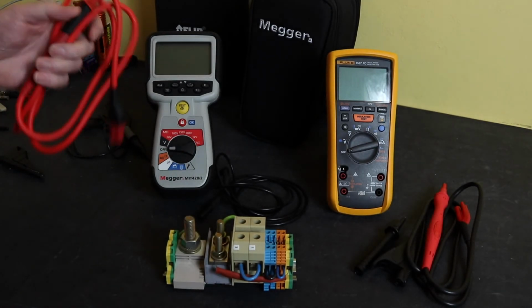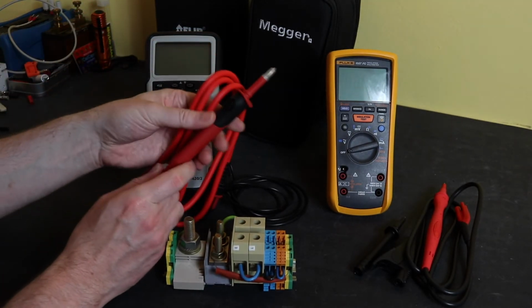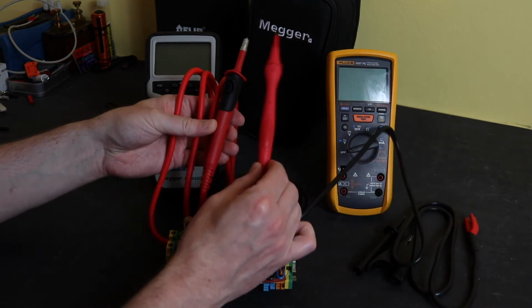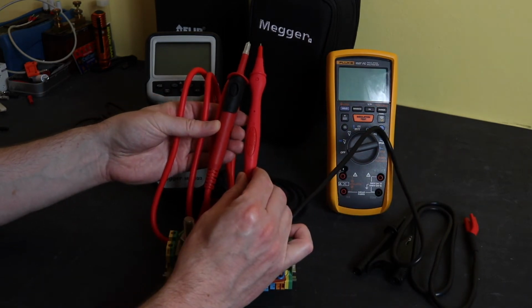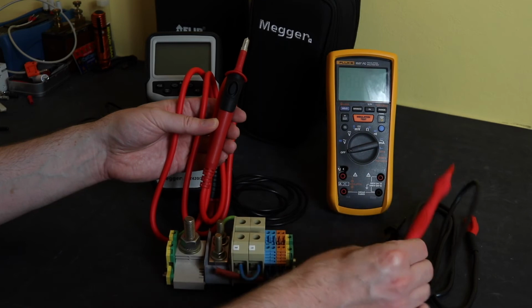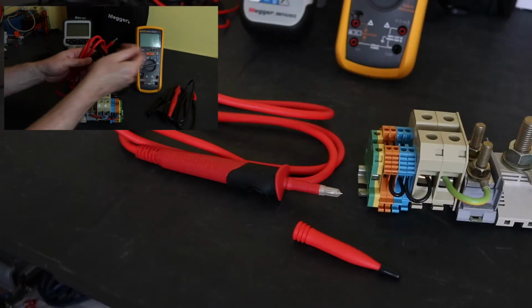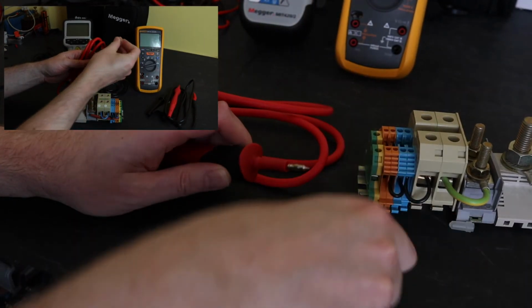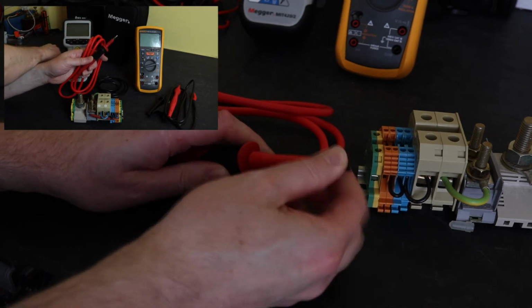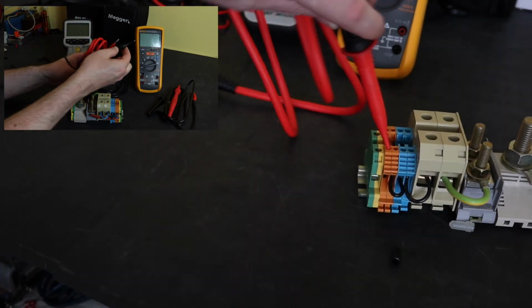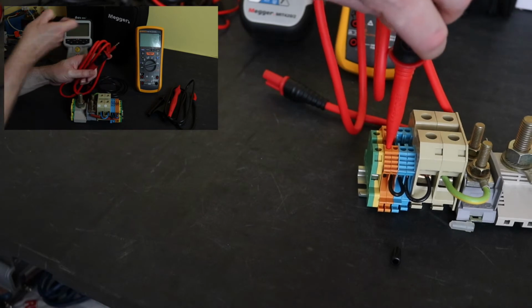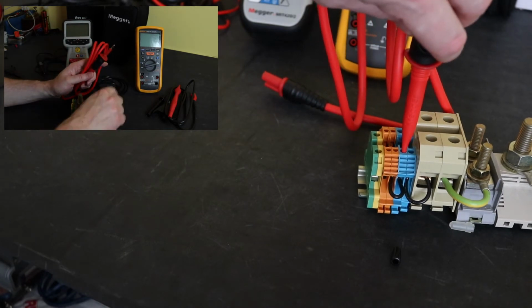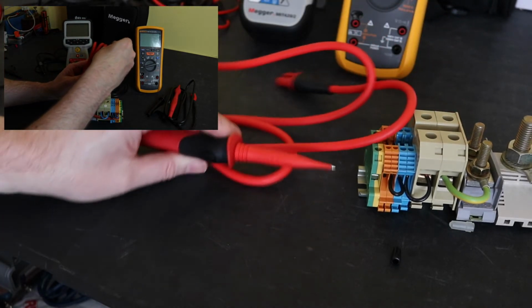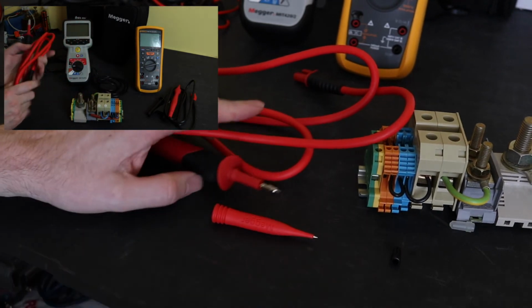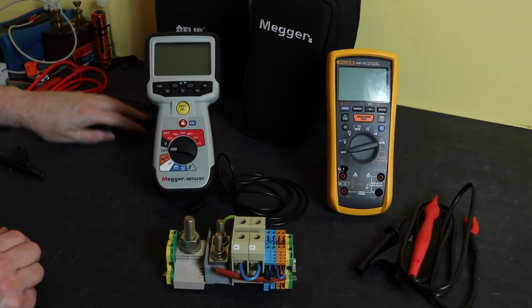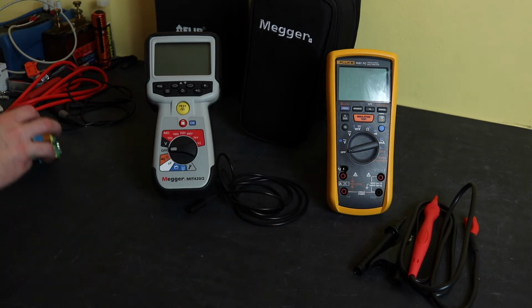The actual probe from Megger is quite a bit bigger, fatter than the one from Fluke. And you do get a special accessory that goes over the top of this, so you can take the GS38 cap off and you get another probe tip very similar to their standard one here, much longer, that goes over this and gives you GS38 compliance and access into all these small terminals there. So that's that one. Chuck them out of the way.